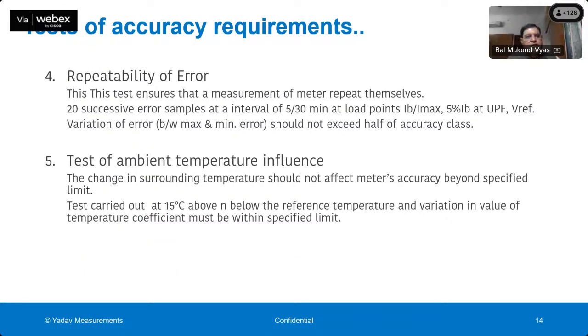Then another important test is repeatability of error, because the uncertainty of the metering is dependent on how repeatable the meter is. The error of the meter is tested, let's say, 5 or 6 times at different load conditions, and 20 successive error samples are taken at intervals of 5 to 30 minutes, and the difference should be less than half of the accuracy class.